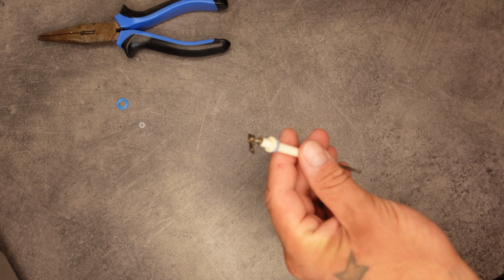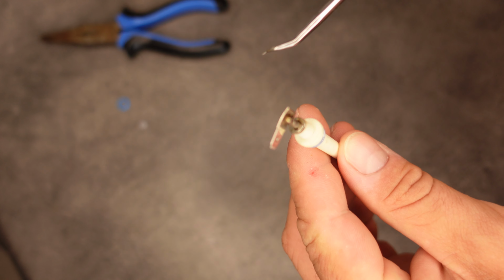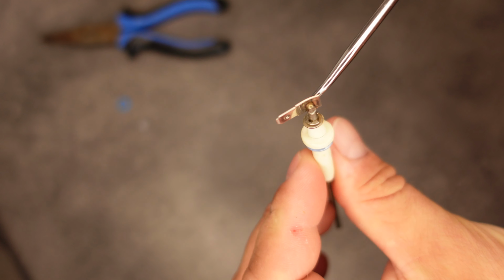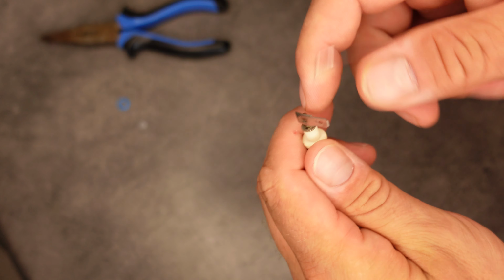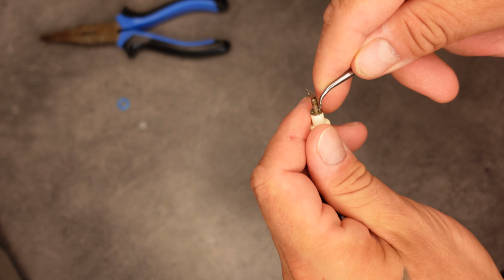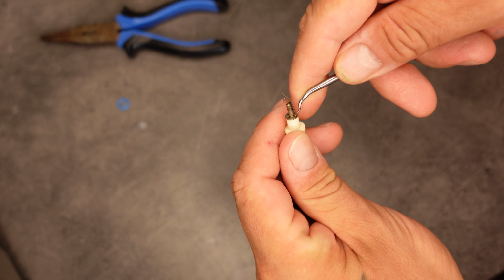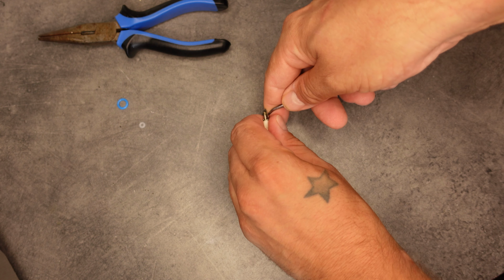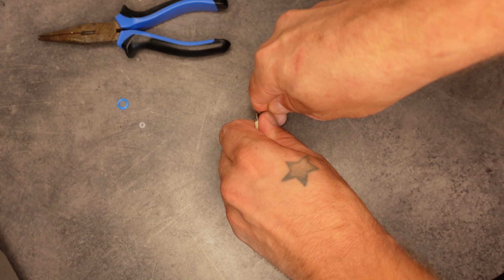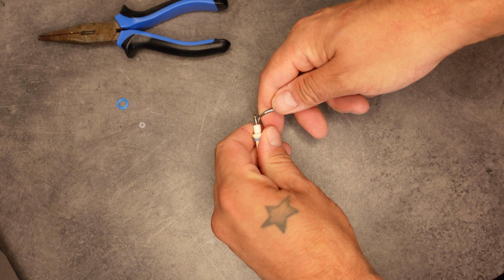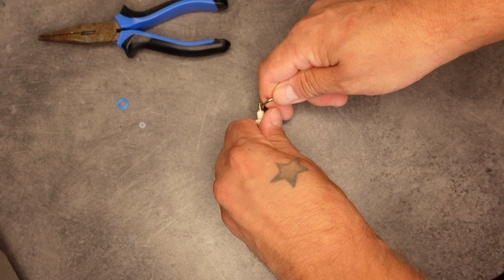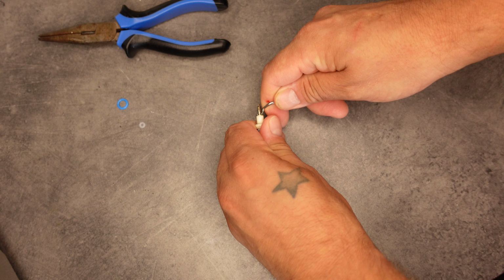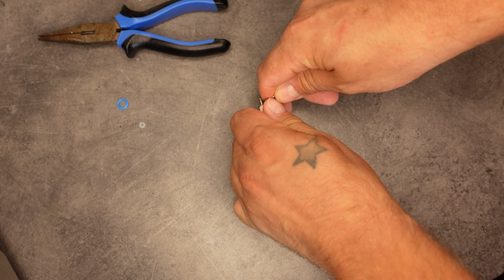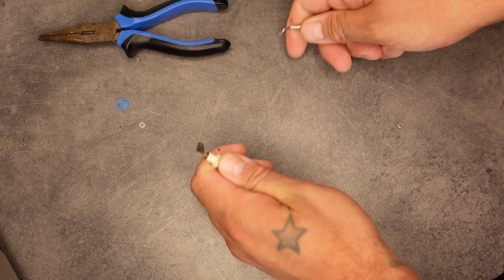The first step is to locate the small locking ring at the top of the probe, which holds the entire insulator in place. Carefully use your pointed tool to remove the locking ring. As you can see, you really need to be careful here. The locking ring can easily fly off or get lost, which is why I try to keep a finger behind it. There you go.